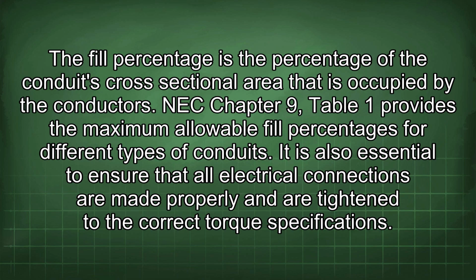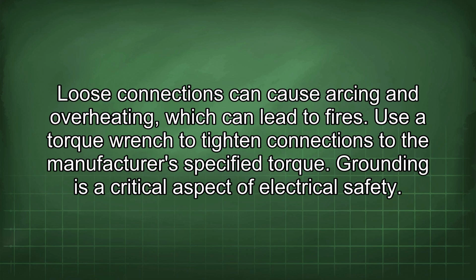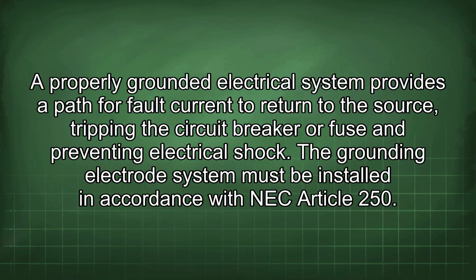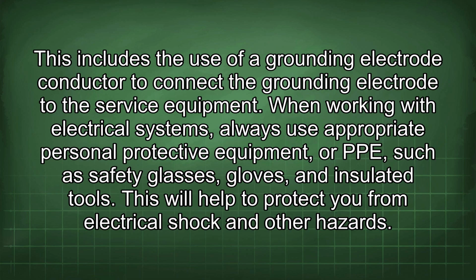It is also essential to ensure that all electrical connections are made properly and are tightened to the correct torque specifications. Loose connections can cause arcing and overheating, which can lead to fires. Use a torque wrench to tighten connections to the manufacturer's specified torque. Grounding is a critical aspect of electrical safety. A properly grounded electrical system provides a path for fault current to return to the source, tripping the circuit breaker or fuse and preventing electrical shock. The grounding electrode system must be installed in accordance with NEC Article 250. This includes the use of a grounding electrode conductor to connect the grounding electrode to the service equipment.